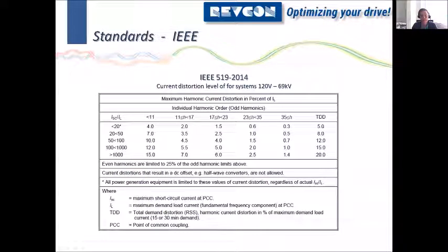And of course, the standards know about this. IEEE 519, for example, will give you individual values for individual harmonic orders, and it limits the total demand distortion, which I will come back to later. This is not only for the IEEE; the IEC will have different ways to handle this and may have different limits, but in the end they all specify individual harmonics and individual limits for certain frequencies. As you can see, for orders below 11 they allow you a lot more harmonics than they allow for 11 to 17 and so on.